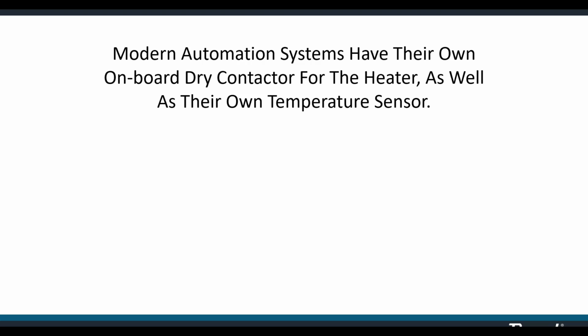Let's talk about remote operation. I get a lot of questions about that. Your modern operation systems, or automation systems rather, will have their own dry contactor on board. That would be a dry contactor for the heater. They will also have their own water temperature sensor that's not attached to the heater at all. They all work the same way.